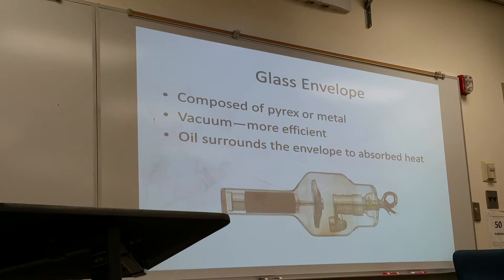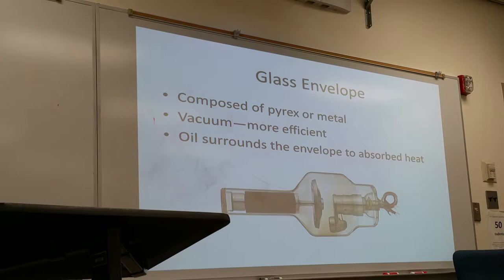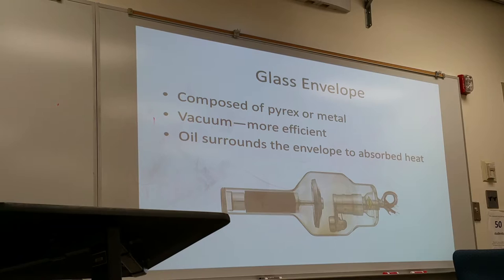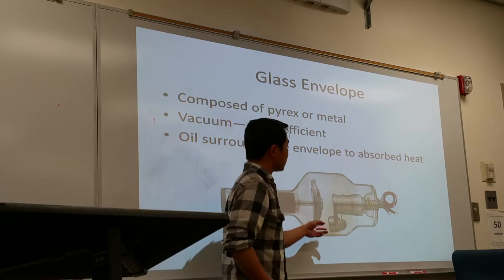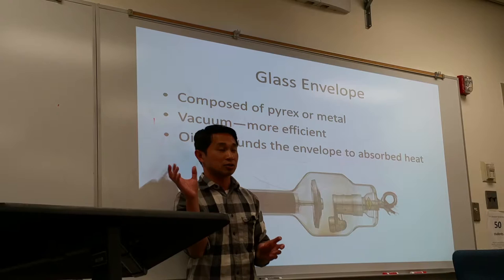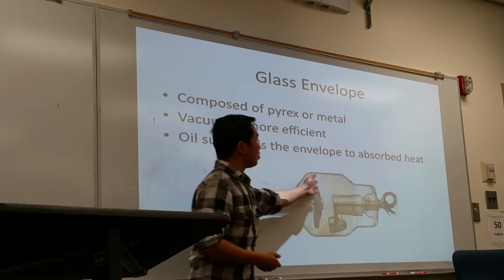The envelope can be a glass envelope or a metal envelope — maybe Pyrex glass or just metal. Within the envelope, it is a complete vacuum — there are no air molecules inside. The reason is that when electrons travel from the cathode side to the anode side, we want a straight projectile without disruptions. If electrons interact with air molecules, they may scatter in different directions, making x-ray production extremely inefficient. So within the envelope, we maintain a vacuum.